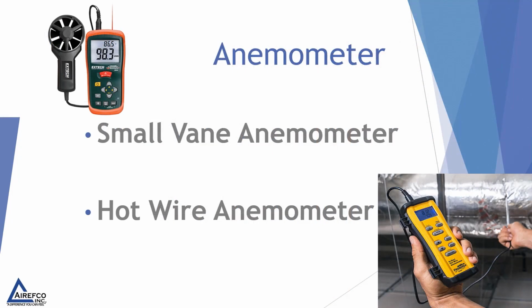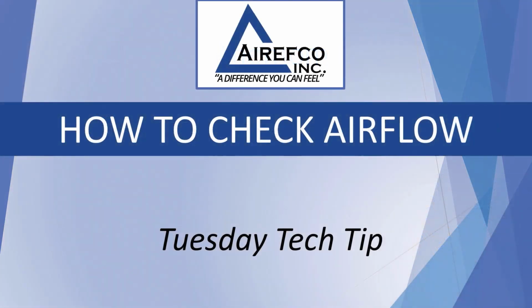Another way to check airflow in a system is by using an anemometer. There are two different types, a small vane type, which has a little fan on it, which when stuck into a ductwork or into the airflow will read CFM or feet per minute on the dial. And then there's also the hot wire anemometer, which is the most accurate of these instruments, and they will read direct CFM or feet per second out of a ductwork.